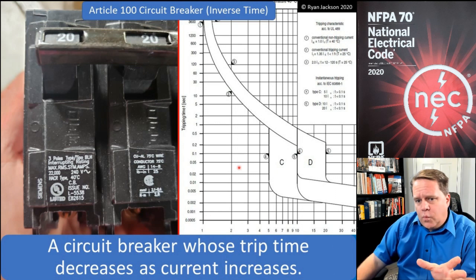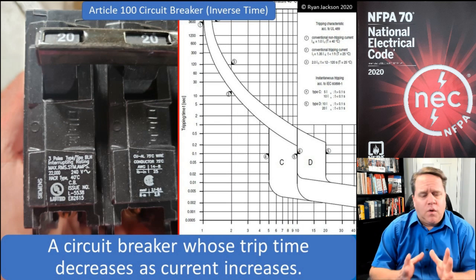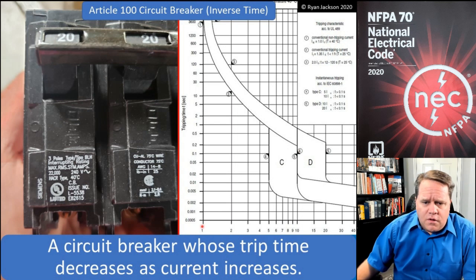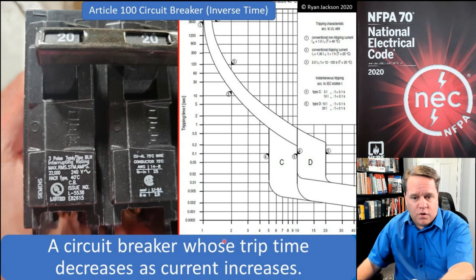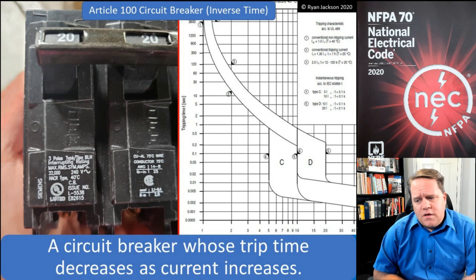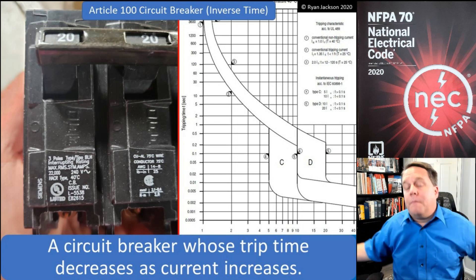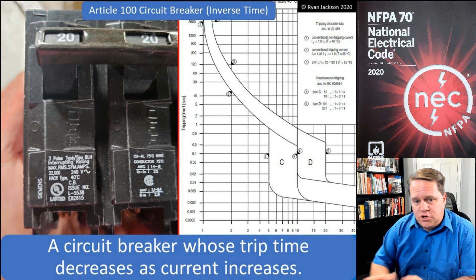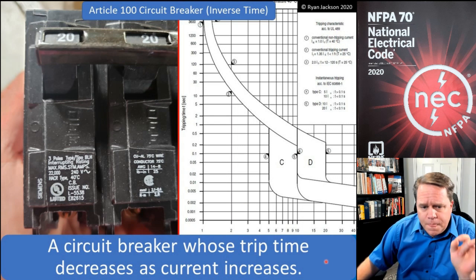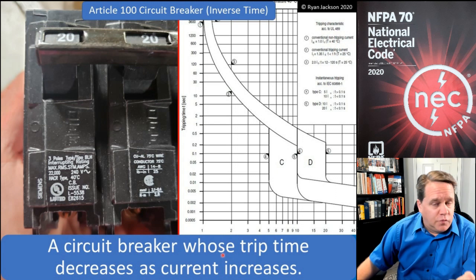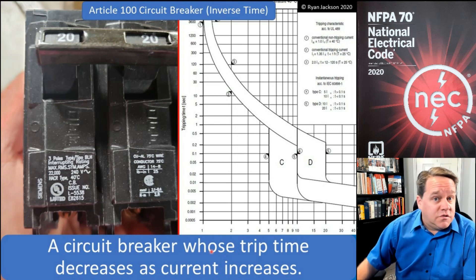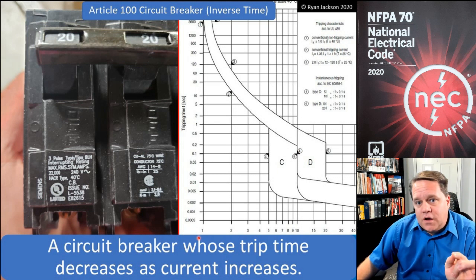When you look at a time-current characteristic curve, it's printed on logarithmic paper, meaning it's not to scale — the distance between 1 and 2 is not the same as between 2 and 3, or 3 and 4. You can see it goes 1, 2, 3, then 10, 15, 20. If we wanted it to scale, we'd need a piece of paper literally a mile long, so we use logarithmic paper. Current on the bottom is shown in multiples of the circuit breaker's handle rating.